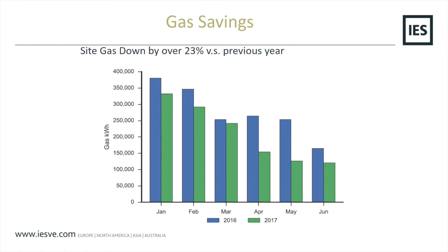On the gas side, the savings were better, so 16% savings electrically in that first year. We got up to 23% on the gas. Combined, you get a near 40% energy savings. So it's definitely an example of retro engineering through better data. It's important to say with this site that we didn't actually spend any money other than the consultancy fee. So there's no capex going on additional hardware. Those savings were really achieved through just looking at the data, the retro engineering approach to it.